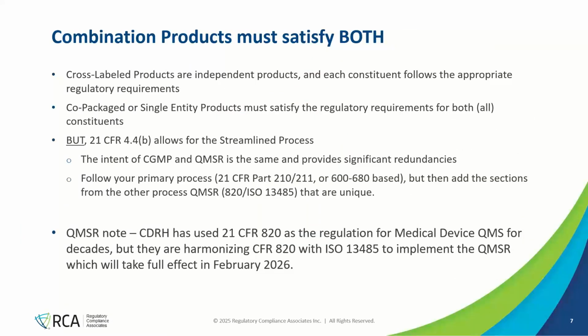So your combination products have to satisfy both quality management system regulations. Cross-labeled products, if you are mandating that your drug get delivered with a specific device, then that specific device may never enter your facility. You may never have hands on it. So that can be totally managed under its own quality management system, and your drug managed under its own quality management system, and those two do not have to touch. But if it's co-packaged or if it's a single entity, you have to satisfy both the drug and device quality management system regulations.